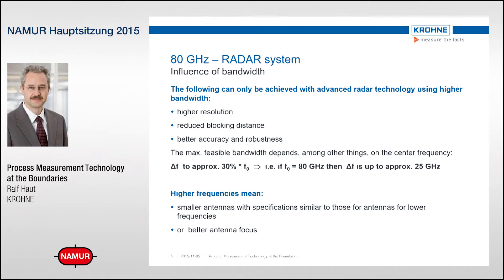The bandwidth of a center frequency plays an even bigger role than estimated. To achieve higher resolution, reduced blocking distance, better accuracy and robustness, advanced radar technology using higher bandwidth is required. There is a rule of thumb: bandwidth is approximately 30% of the center frequency. So with 80 GHz, the bandwidth can be up to 25 GHz.